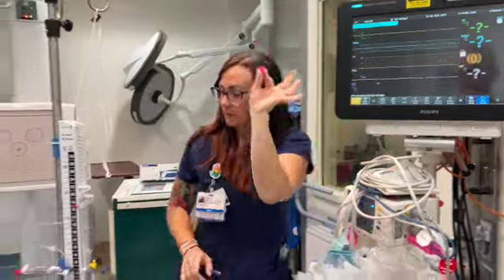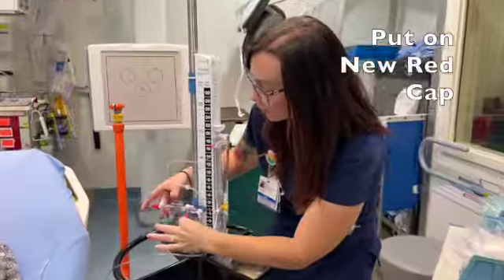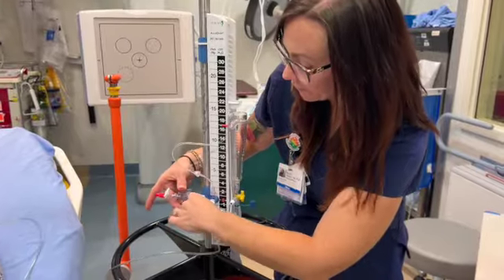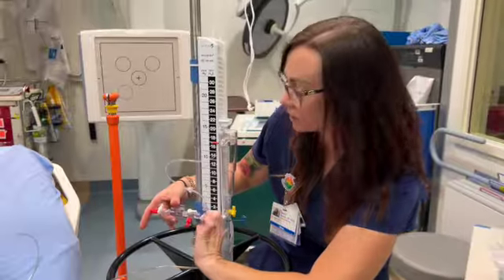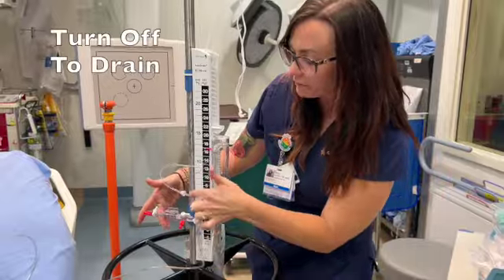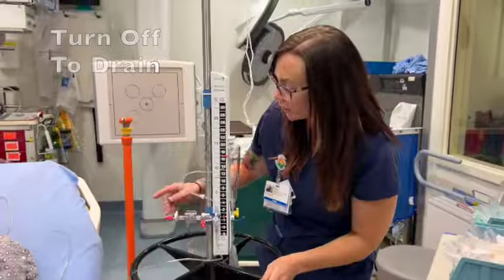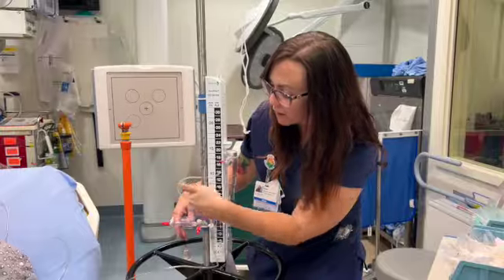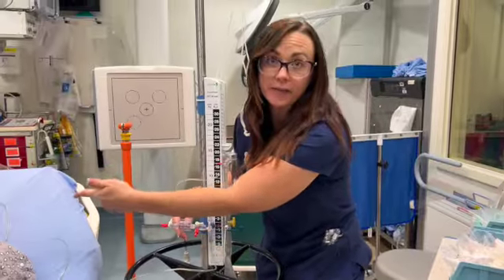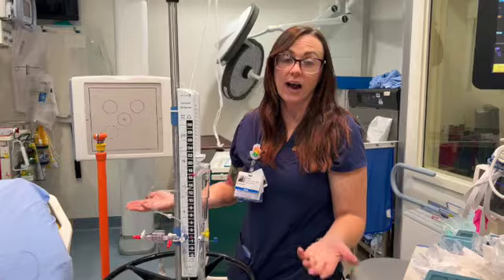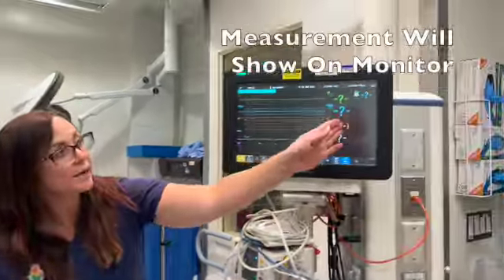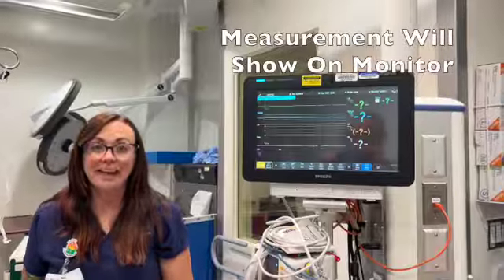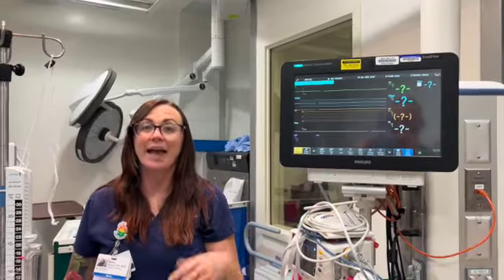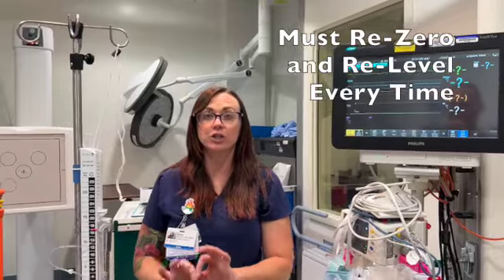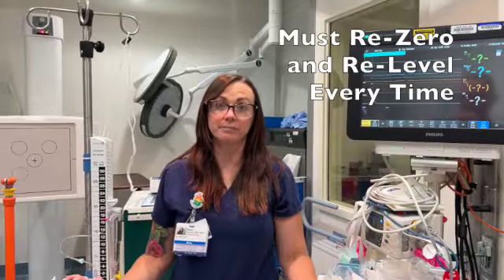In order to do that, we're going to take a new red cap from the IV cart, place it to our device here. We're going to take our stopcock, and we're going to go off to the drain, and that way we ensure that there's a clear line from the transducer to the patient's brain. And from there, we're now ready to measure ICP. You will see a measurement come up on the screen once you've done that. Again, you're not able to measure ICP and drain CSF at the same time. When you switch back and forth between the two, you need to make sure to re-zero and re-level each time.